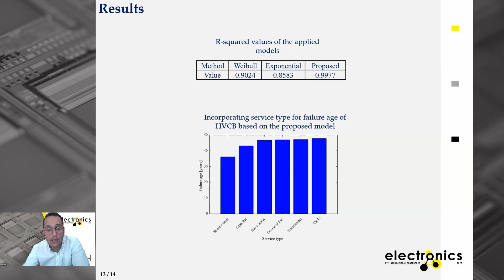As I mentioned, we also incorporated the service type. So if the age is around 45 years and it's used for cables, you'd expect the circuit breaker to be aged more. However, if it's used for shunt reactors, after normalization, it could be around 38 years or even less, depending on condition. This is how we incorporated service type into our results.